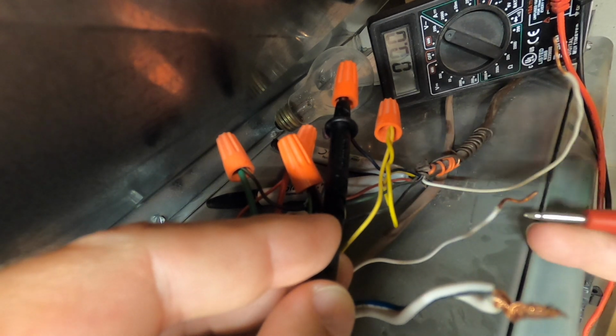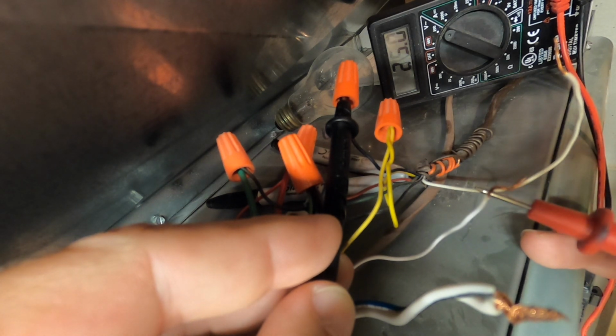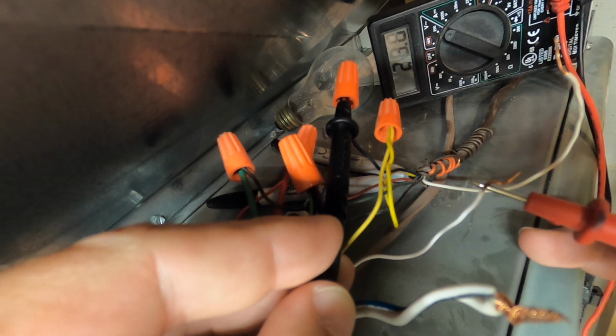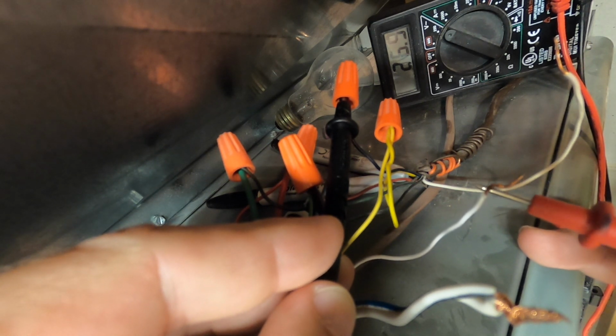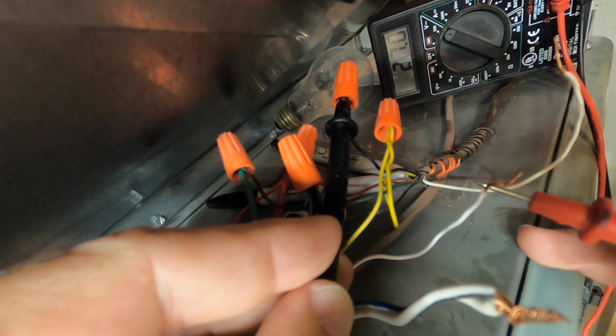No voltage. And this one is coming from the condenser outside. Oh, looky there, we got voltage. We got 26, 27 volts. So the outside unit is, for some reason, telling the electric heat to come on while in cool mode.